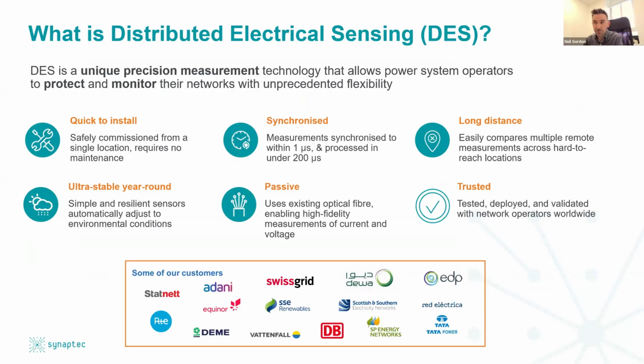DES is Synaptec's unique precision measurement technology. Very briefly, what this technology lets us do is deploy passive point sensors for current, for voltage, and for temperature over very wide areas on power networks using the existing single mode optical fiber network. This enables many protection and monitoring applications for operators that without a technology like this would be hugely expensive to deliver. The technology is very quick to install because it requires, as you'll see in a moment, no supporting infrastructure at each measurement location.